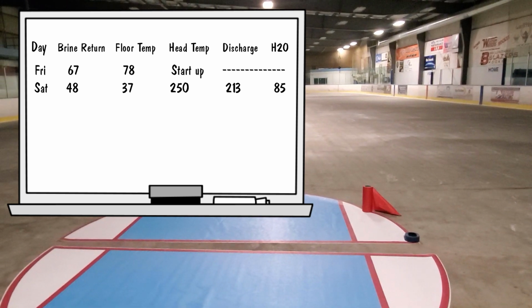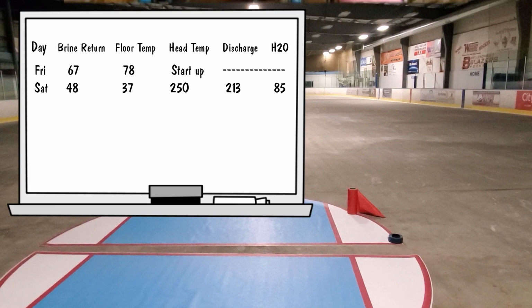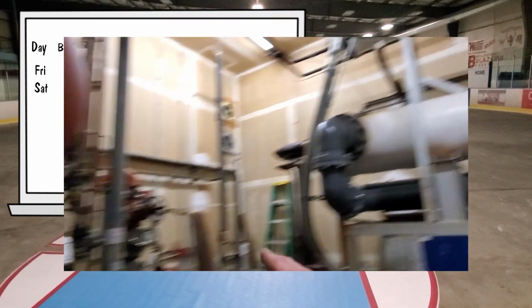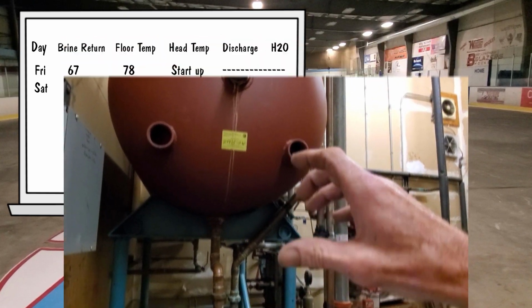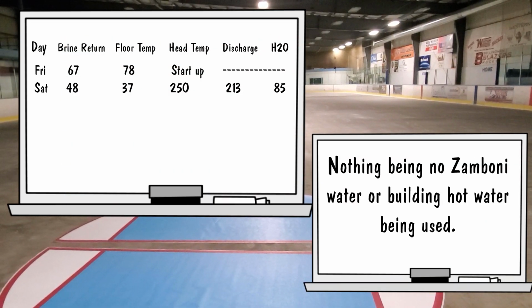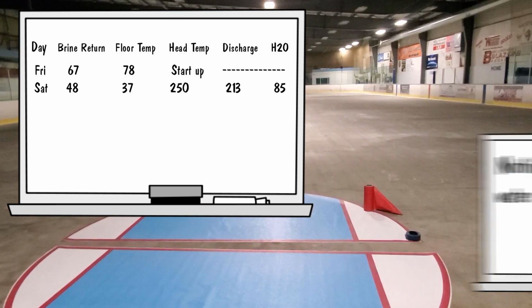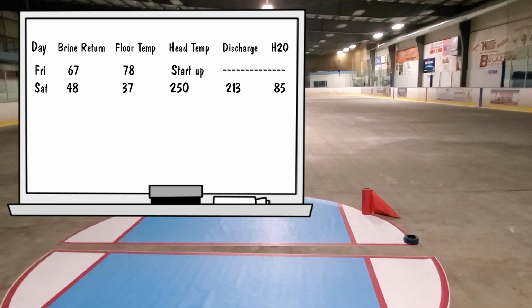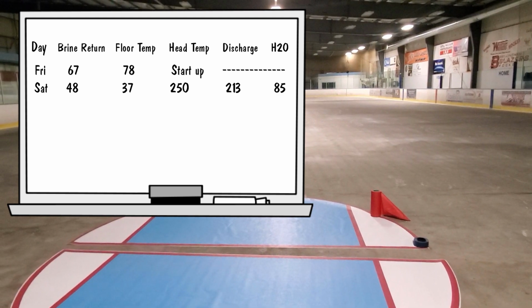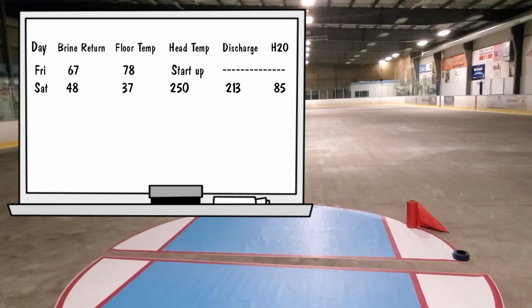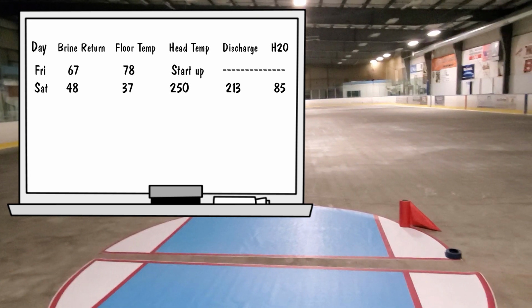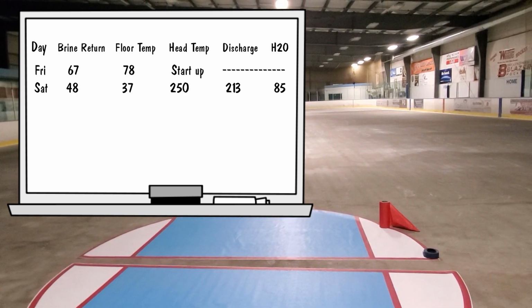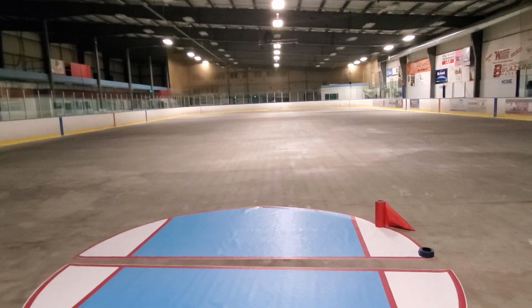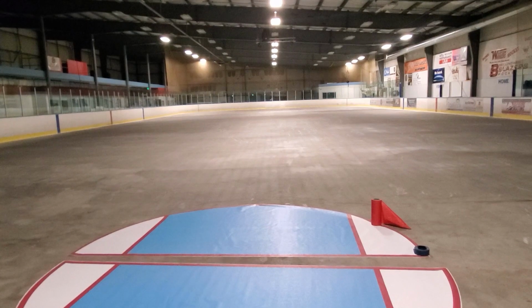Since we have a heat recovery system, I'll throw a video in here, if I didn't delete it, showing me going back and forth between the heat recovery, the heat exchanger, and the storage tank. Water is circulating between those things, but since nothing is being pulled out of the system, that water was getting hotter and hotter. Usually that has to be running anytime the system's running, because if it's shut down and the system's running, that heat exchanger can become a steam bomb. So having that thing really hot with hot water is not a good idea.